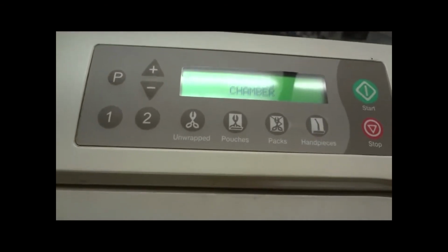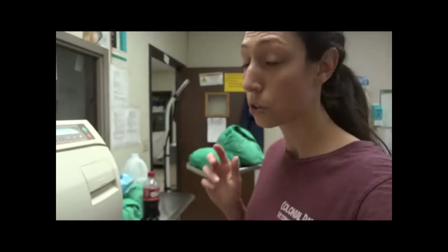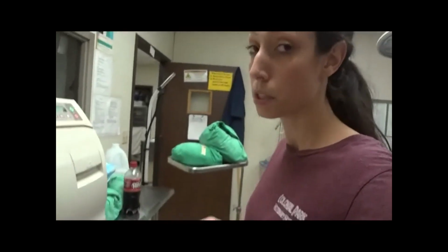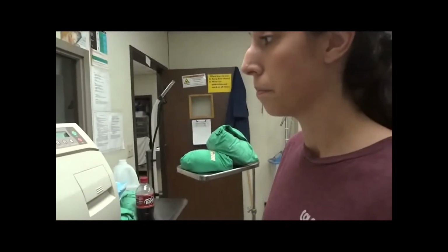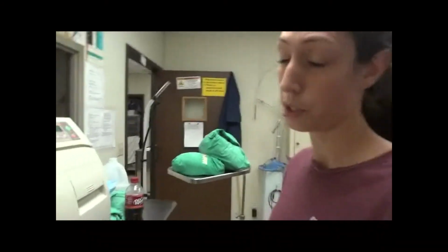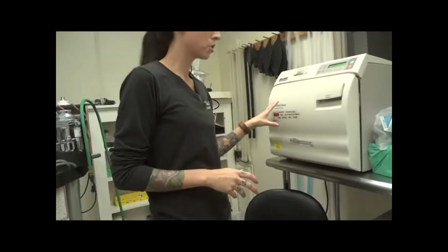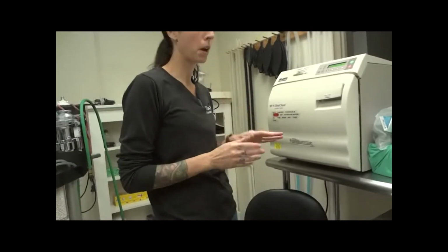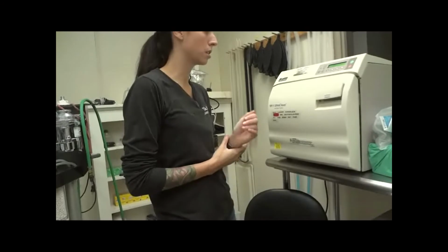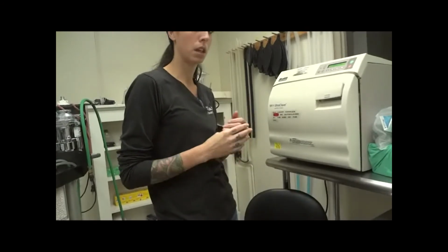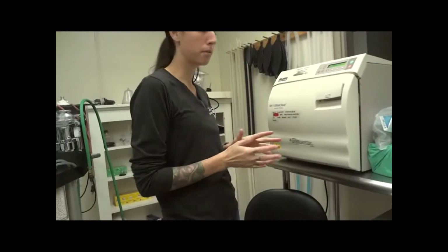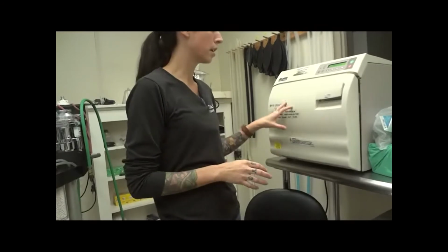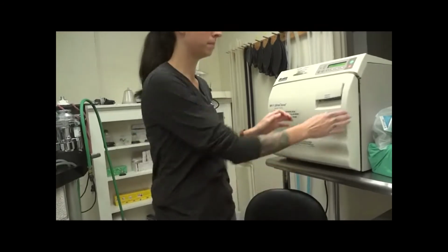So it's filling the chamber now. It's going to start. So it's going to sterilize our packs through a heated steam system. There's also cold sterilization, but my clinic does not use that. The proper temperature of an autoclave should reach about 120 degrees Celsius. The pressure should reach 15 psi, and the cycle runs for 30 minutes.